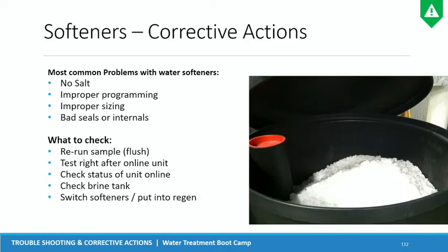Other systems, you're adding 20, 40 bags a day. And so pretty quickly, you can empty out that brine tank if you're not staying on top of that. Programming bad, see that quite often. You get into a plant, maybe something was wrong and they thought, oh, well, I'll just change the settings on the softener and that should help out, right? And then it's no longer programmed properly, so it's not going to work properly.